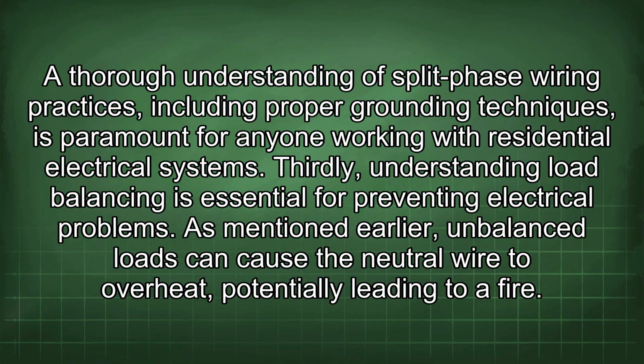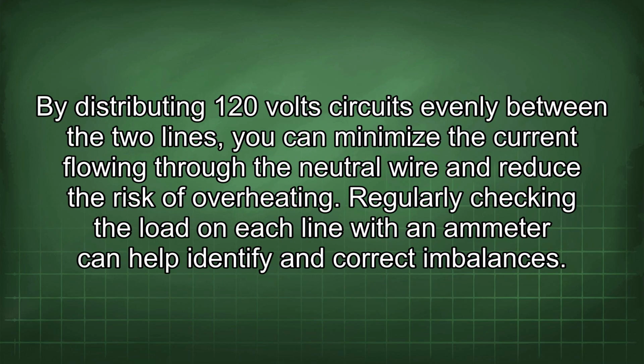Thirdly, understanding load balancing is essential for preventing electrical problems. As mentioned earlier, unbalanced loads can cause the neutral wire to overheat, potentially leading to a fire. By distributing 120 volt circuits evenly between the two lines, you can minimize the current flowing through the neutral wire and reduce the risk of overheating. Regularly checking the load on each line with an ammeter can help identify and correct imbalances.